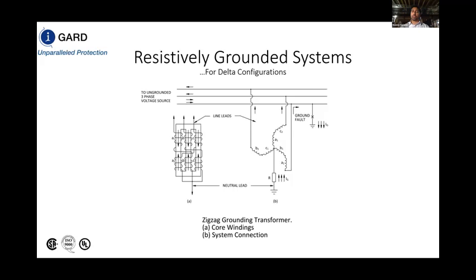This resistor does quite a few things for the system. One, it controls the transient overvoltage scenario that would otherwise occur in an ungrounded system. Two, it provides a ground return path for the ground fault that is occurring in the system so that we can actually quantify how much magnitude that ground fault has. And in addition to that, we're able to locate the position of the fault provided that this resistor has a pulsing feature, which we will get into shortly.